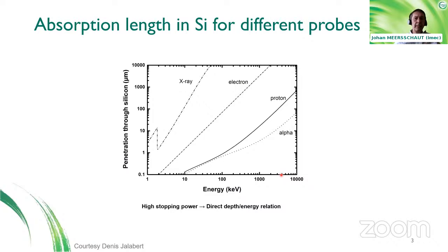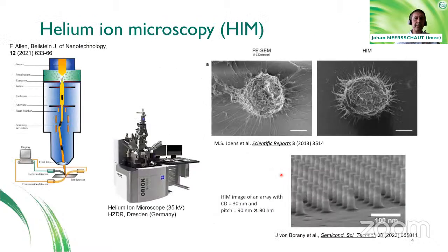The characteristics that we will probe are substantially different depending on the energy that the primary ions have when they hit the sample. At the lowest energy that we were talking about, the ions will mainly hit the outermost surface of the sample. On this graph here, you see the representation of a helium ion microscope, for which the ions are accelerated to about 35 kilo electron volt.